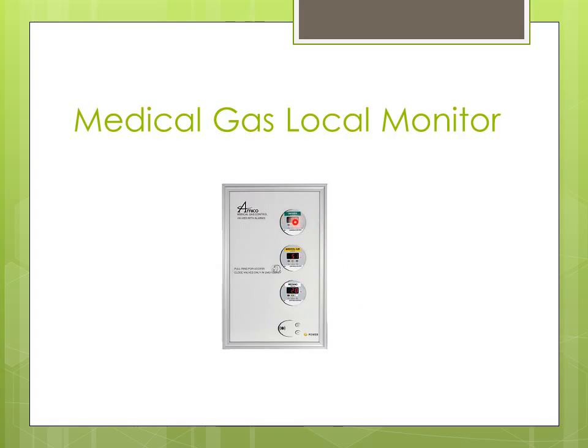Each one of these will have the amount of pressure, and they will alarm if those pressures go out of range. And these are typically, again, located outside of rooms. Sometimes they might be inside of rooms. But it's important to know, too, that if they're going to be located in the room, there's going to have to be valves outside the room as well. Typically, these are all located outside the room.